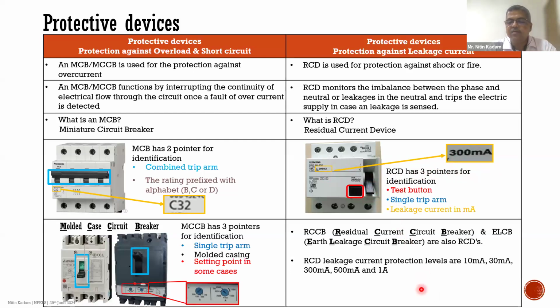Previously, the earth leakage circuit breakers were used, but now the RCDs are used, and generally the RCCB or the ELCB is now called an RCD. And the protection current values or the leakage current values for which the RCDs are generally available are 10 milliamps, 30 milliamps, 300 milliamps, 500 milliamps, and 1 amp or 1000 milliamps.